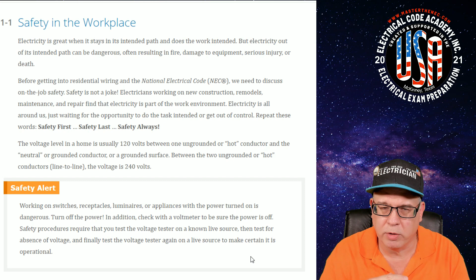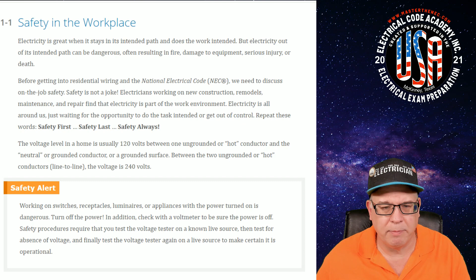You need to make sure your voltmeter works perfectly fine before you rely on it, and the same goes for those little tickers. Check them on a known source before assuming something is de-energized, since it could be a bad voltmeter or a bad tester. Safety practices are paramount: test on a known live source, then on the circuit or equipment you're working on, and validate that it's de-energized. Making sure your tools are operational and in good working order is critically important, and every electrician should know that right off the bat.